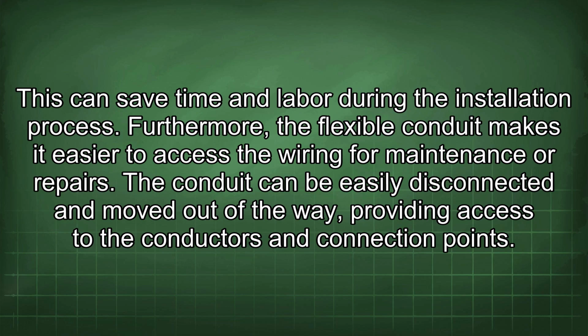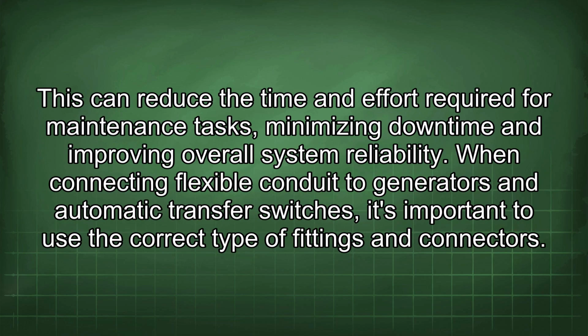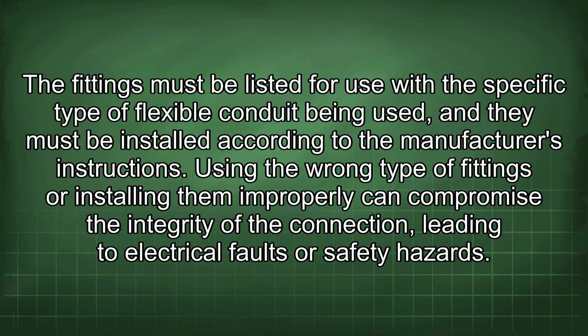The conduit can be easily disconnected and moved out of the way, providing access to the conductors and connection points. This can reduce the time and effort required for maintenance tasks, minimizing downtime and improving overall system reliability. When connecting flexible conduit to generators and automatic transfer switches, it's important to use the correct type of fittings and connectors. The fittings must be listed for use with the specific type of flexible conduit being used, and they must be installed according to the manufacturer's instructions.